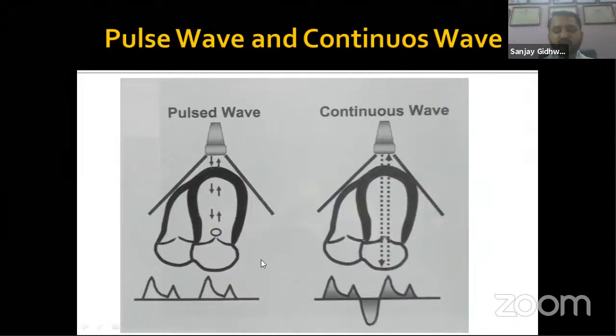These are usually used to see whether the particular segment, pulse wave means same level at a single point we see. Single point means I want to see this point only. So I would arrange the probe and transducer, catch a pointer to this area and release the pulse. Pulse means nothing but a short wave that I want to see the particular segment. Suppose I want to see the mitral valve, only this wave will be transmitted to that particular area and will be reflected from that point only. If I want to see the atrium, then I have to push the pointer to this area. If I want to see the LV apex, then I have to put the pointer to this area.